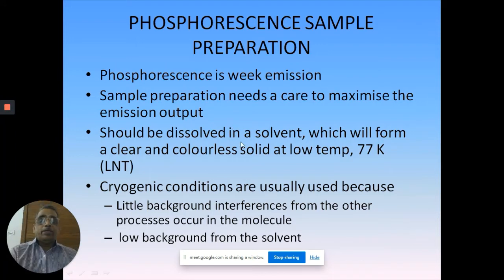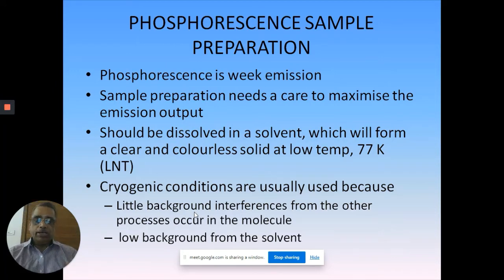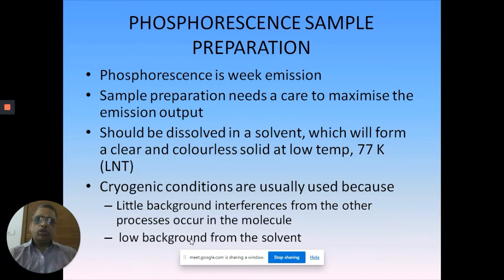When you go for the 77 Kelvin measurement - LNT, liquid nitrogen temperature - cryogenic conditions are usually used. Why? Because we want to reduce background interferences from fluorescence and other phenomena, and also reduce background from the solvent. If you have impurities from the solvent, that will also interfere. Cryogenic conditions will give you almost background-free phosphorescence.